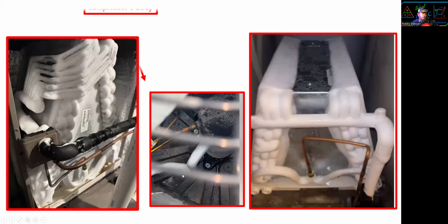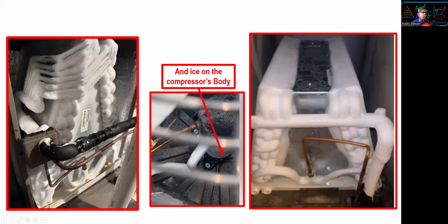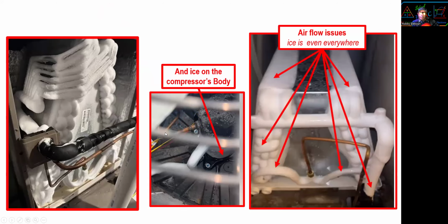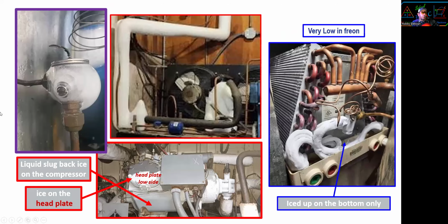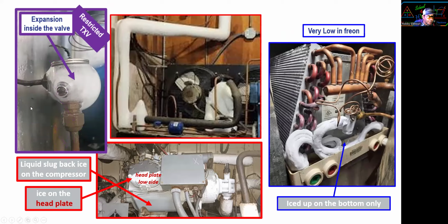Next, ice on the compressor body. Ice even everywhere. Airflow issues. Nothing's wrong with the metering device. Both these are orifices, huh? Yeah, both these are orifice. Okay. This is an airflow issue. Ice is even everywhere. Now, there's your restricted expansion valve already. Expansion inside the valve.